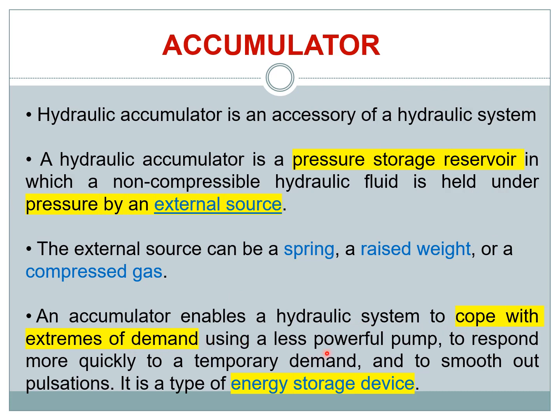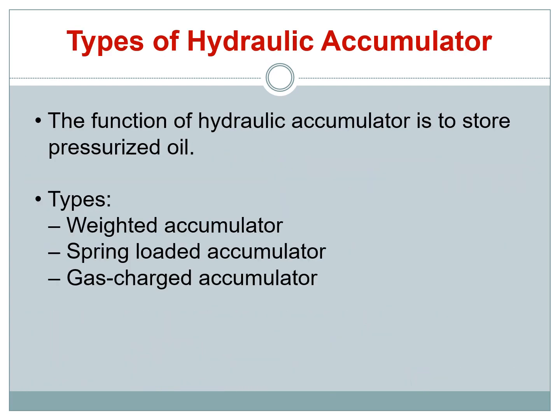The accumulator enables the hydraulic system to cope with extreme demands using a less powerful pump, to respond more quickly to temporary demand, and to smooth out pulsation. This is similar to the reservoir in pneumatics. In case of extreme demand, there is no need to get a new supply because pressurized supply is already available and ready to send. It can also smooth out pulsation, which is a sudden spike or shock in your system. It is a type of energy storage device.